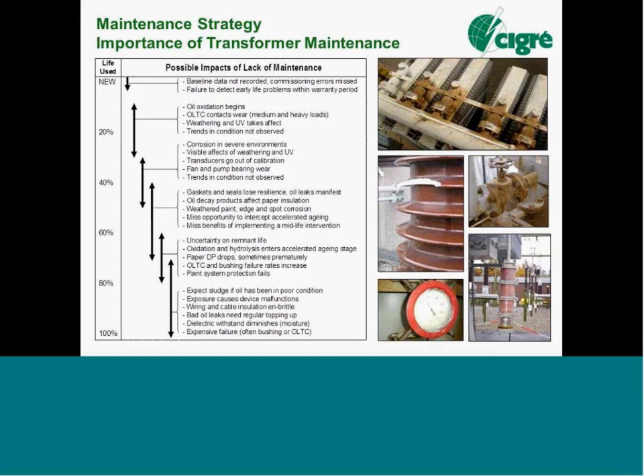Some of the tank fittings, and important components like the fittings and the tap changer, are subject to wear or degradation or moisture ingress, and are compromised and fail catastrophically, or with massive failure of the transformer. So we can start to see that with all of these mechanisms at play, with these typical modes of degradation, deterioration, or failure, for the critical units there must be a large degree of impact when they do fail. So it really boils down, I think, in a lot of organisations, to deciding what is your appetite for risk with your assets and how much you spend on them.